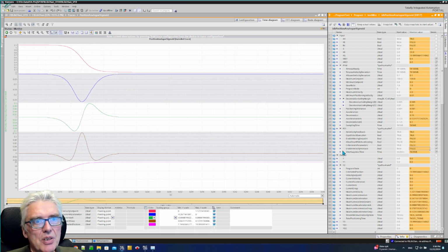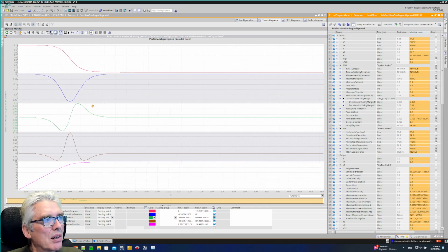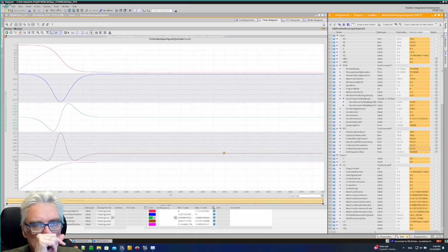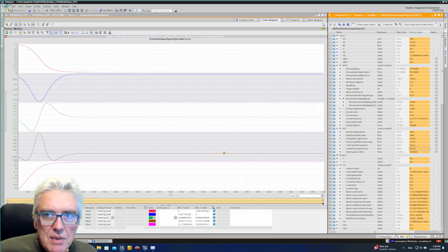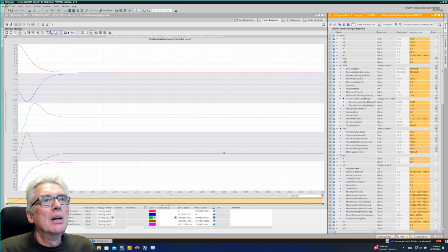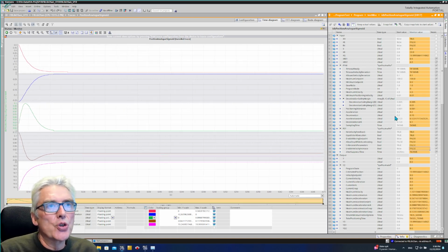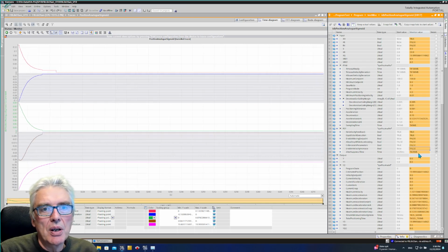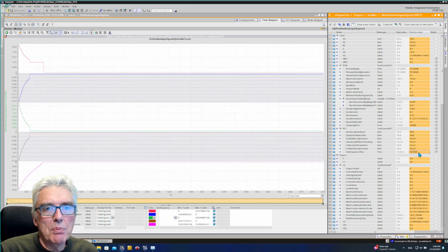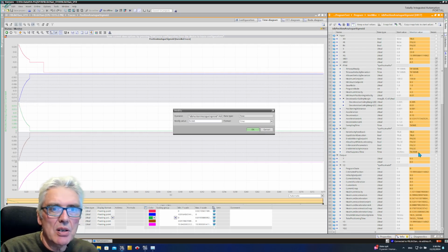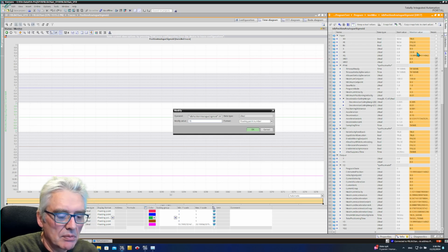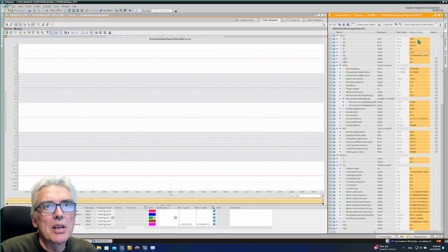And the last one is the jitter suppress time, which you can see now gives kind of nice curves. But when the program starts to accelerate or sets a velocity set, it has to start somewhere, so you are going to get a short jerk or jolt when you start up. Now it's suppressed. But if I set this time to 0 seconds, I register everything. And then we can try to move back to 15. I hit yes, off and on.